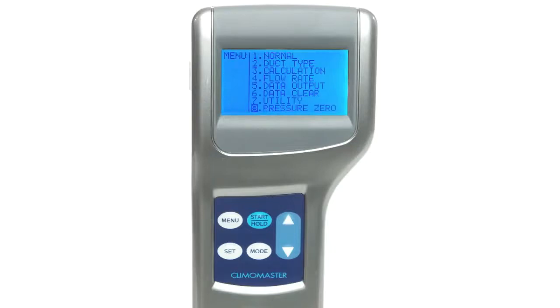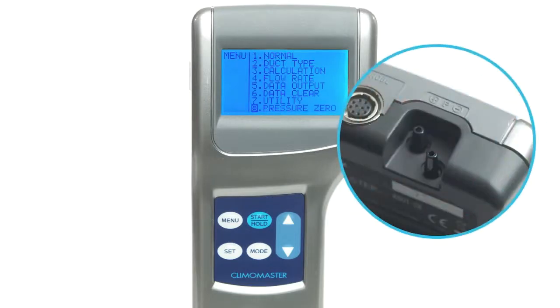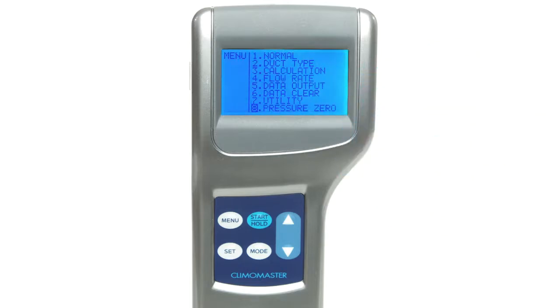Now you're ready to measure pressure using connected tubing on either the positive or negative ports at the top of the device. Whether you're measuring pressure, humidity, air temperature, or air velocity, the duct shape and size settings must be entered beforehand. Up to 25 different duct types can be registered in this instrument, so don't worry about having to repeat this process more than you have to.